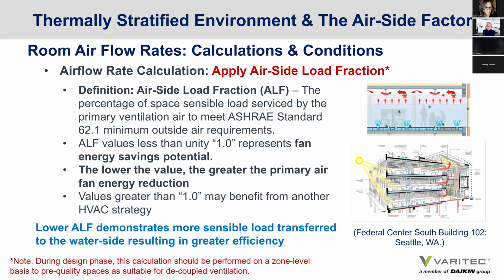You find out what type of sensible cooling effect is present within the outside air being supplied to the space. And that defines how much supplemental sensible load needs to be addressed to maintain space temperature set points at thermostats. And then you look at the certified performance of a radiant panel or sail, see how much sensible cooling they offer at the available chill water temperatures supplied to them, and then see if the capacity meets or exceeds the sensible load to the space.